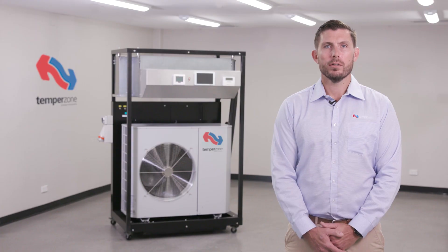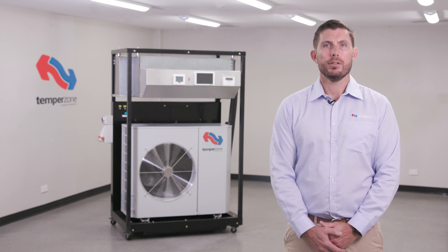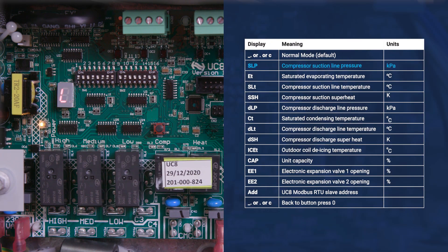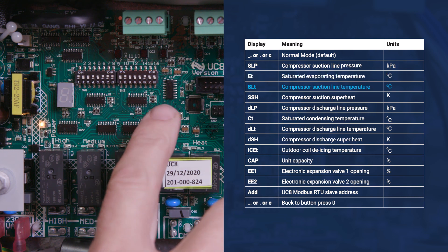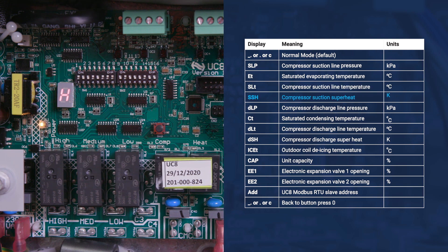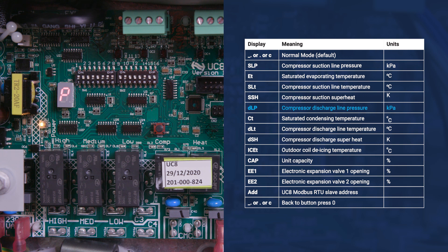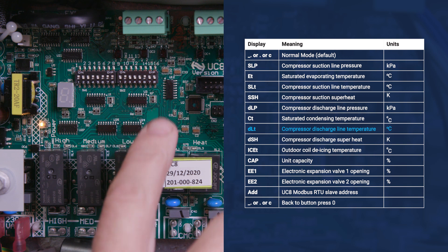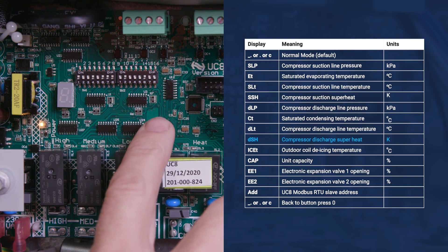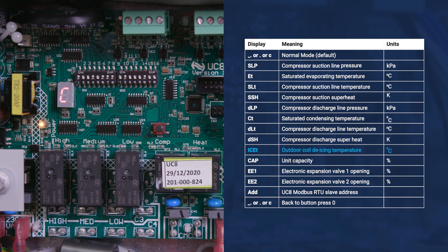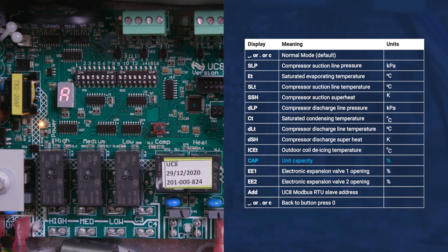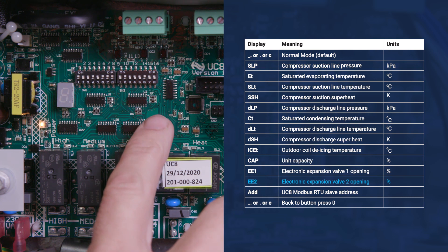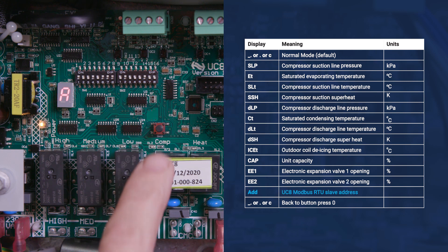UC8 controllers of all software versions identify unit conditions with single presses of the UC8 push button. These include suction line pressure, evaporating temperature, suction line temperature, suction superheat, discharge line pressure, condensing temperature, discharge line temperature, discharge superheat, de-ice temperature, unit capacity, electronic expansion valve 1 position, electronic expansion valve 2 position, and modbus address.